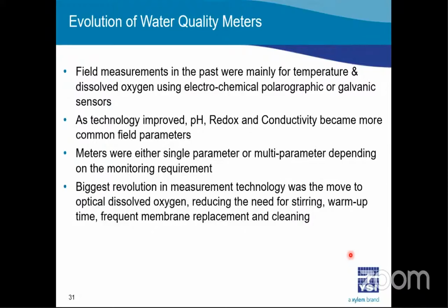Then, in recent years, the biggest revolution we've had is the optical dissolved oxygen sensor. It's actually reduced the need for stirring, warm-up, membrane change, and cleaning of the DO sensor. So now we've progressed to have optical dissolved oxygen sensors.